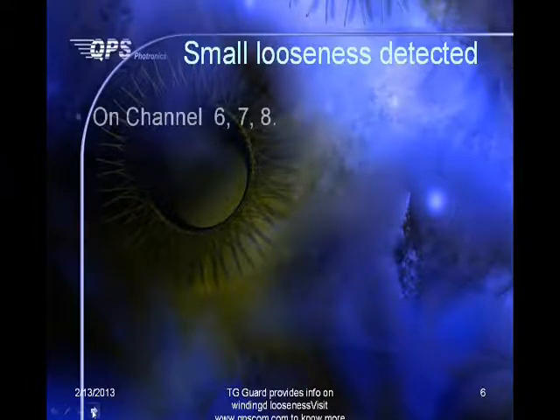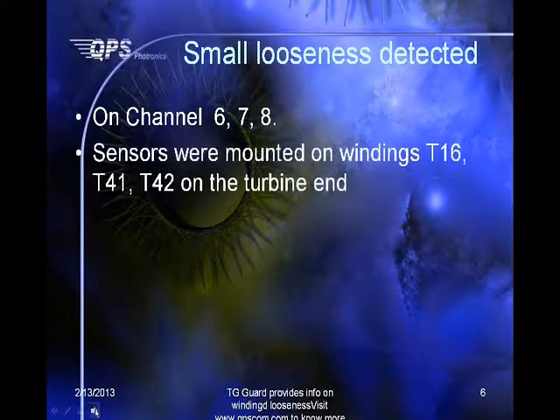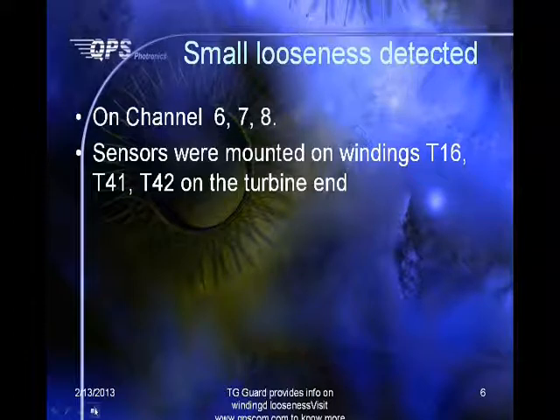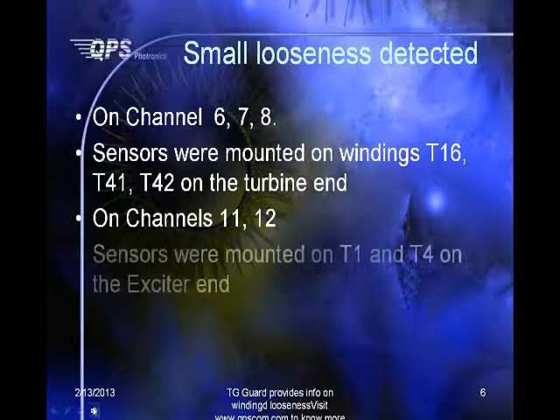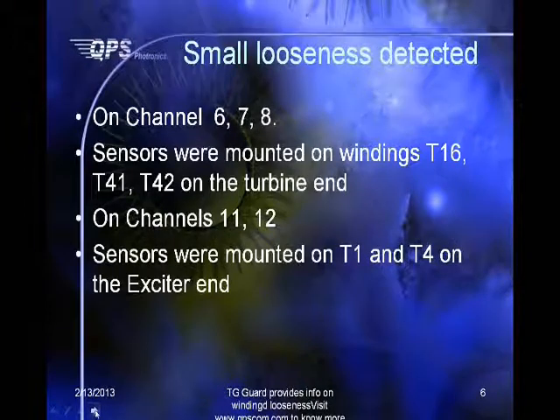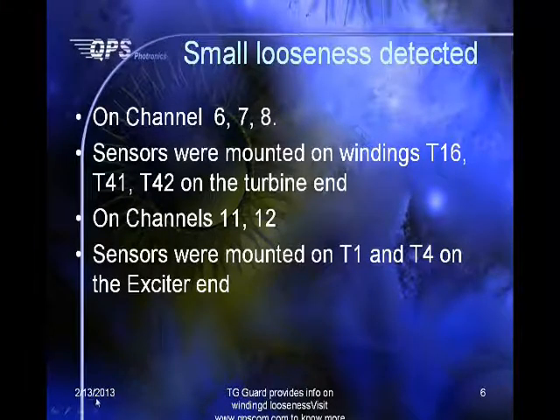So we are suggesting from the vibration amplitude there's a slight looseness developing, but it's nothing of major concern. So I'd like to summarize it first up front. On channel 6, 7, and 8, the sensors are mounted on T16, T41, and T42 on the turbine end. They are showing a slight increase in amplitude. Well, how do I compare? I take the minimum vibration amplitude and compare with the largest amplitude.